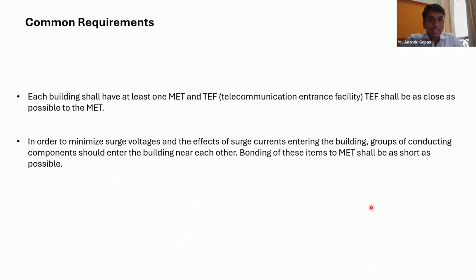So, general requirements: any telecommunication building should have its own telecommunication entrance facility. Basically, the place where all of these telecommunication network related things enter your facility, and you should have an MET to connect all the extraneous and metallic parts in that region to the MET. So it is a requirement to at least have one MET at that region. That region is called the TEF, telecommunication entrance facility. Basically, this is to limit the surge into the building.